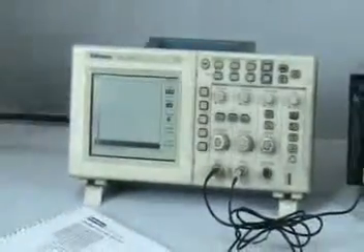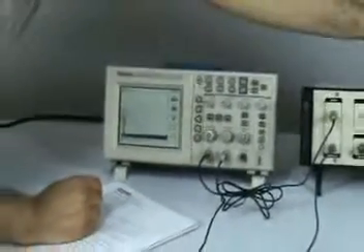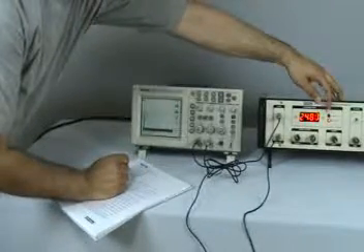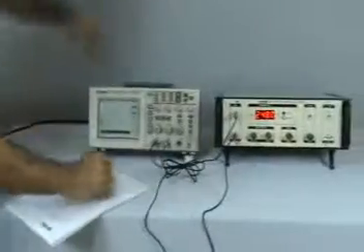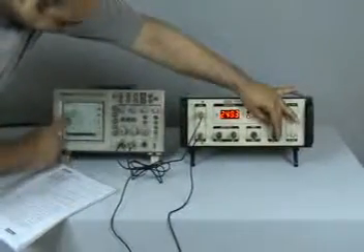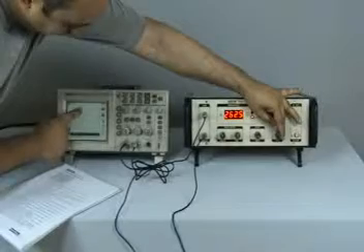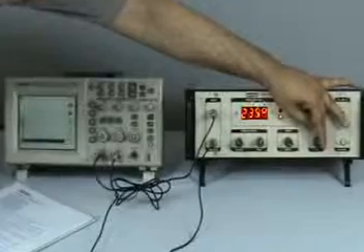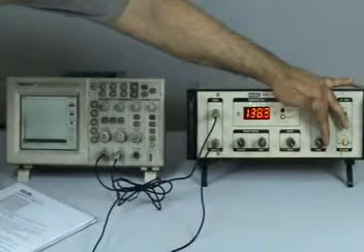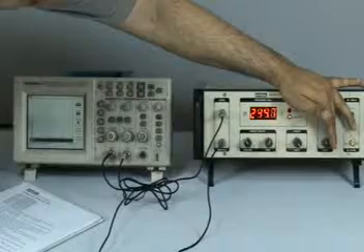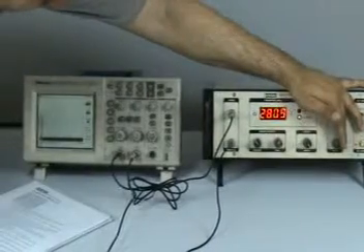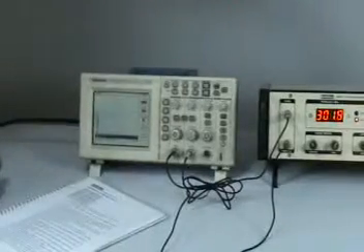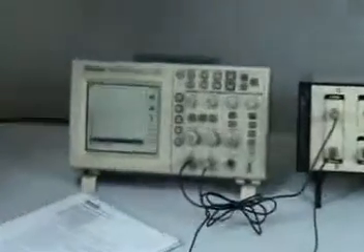The equipment can also display a marker which can be enabled. Now this LED is being shifted to the marker, and the marker will cause a vertical marker on the CRO to be displayed, and any movement of this control will move the marker in the horizontal axis, and any frequency component can be read off by overlapping the marker with the frequency component in the display.